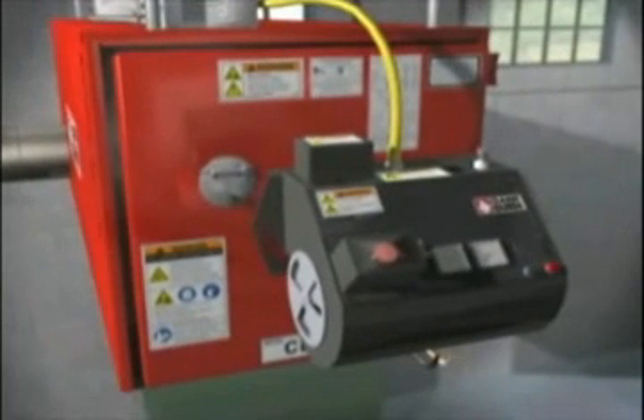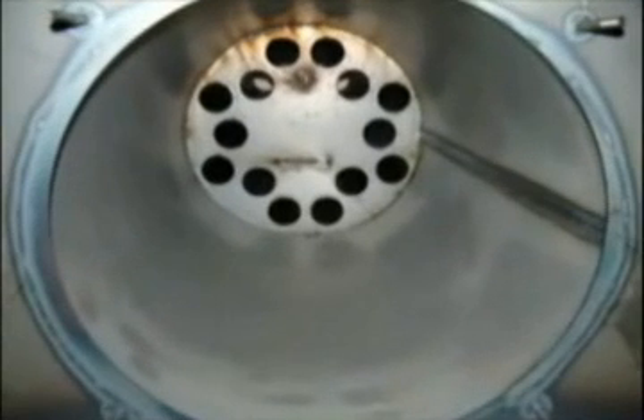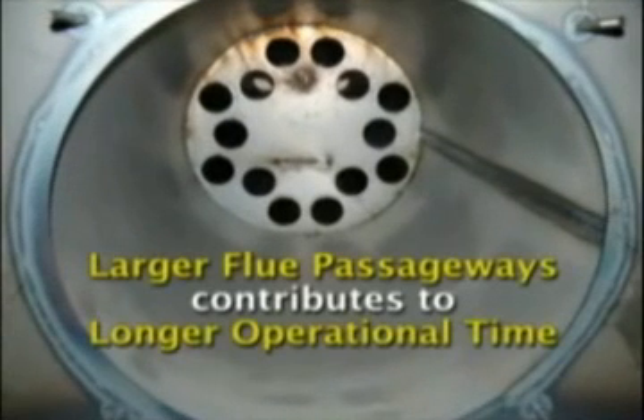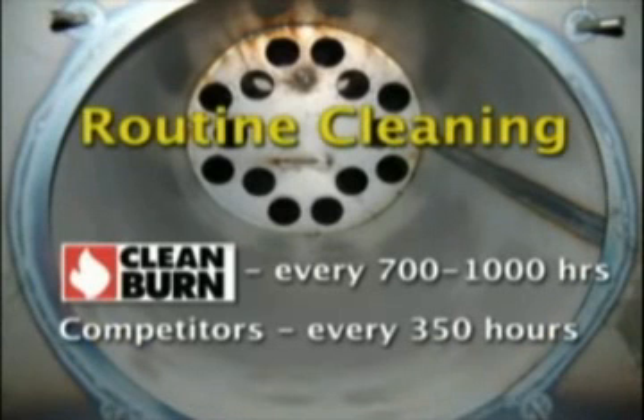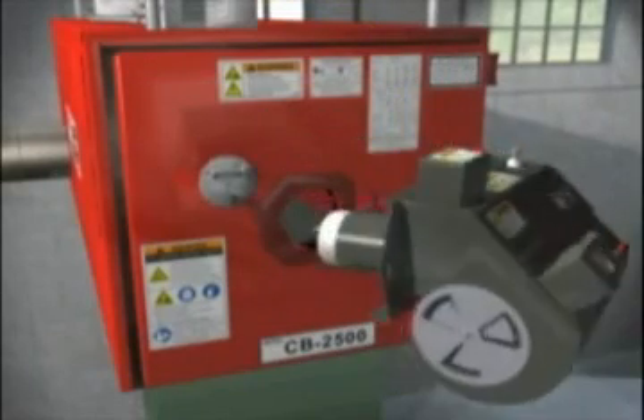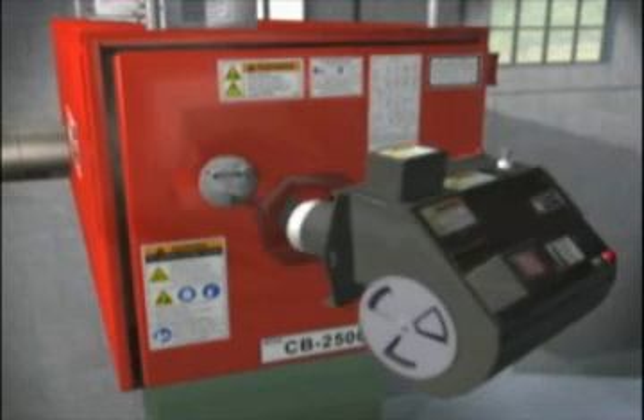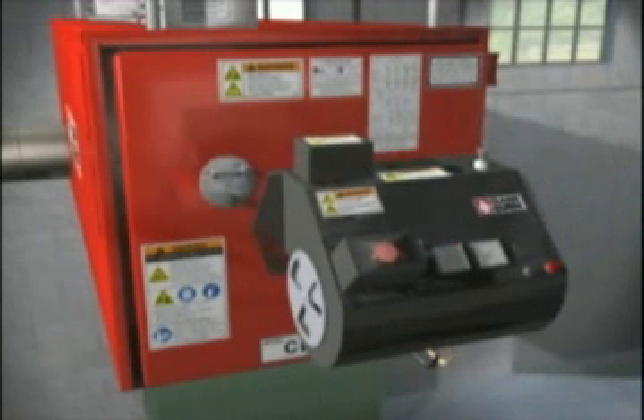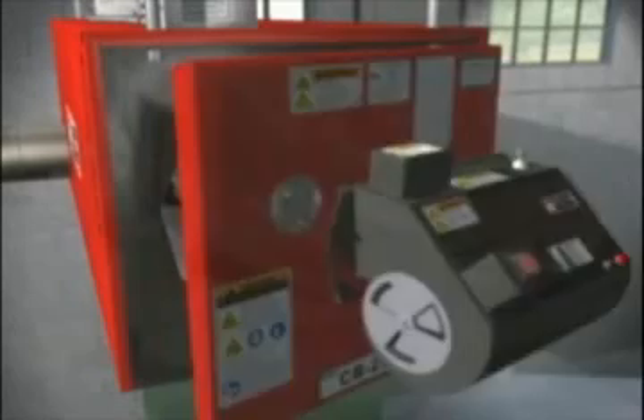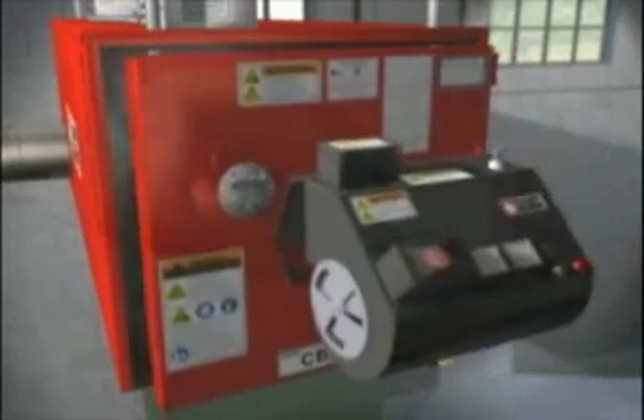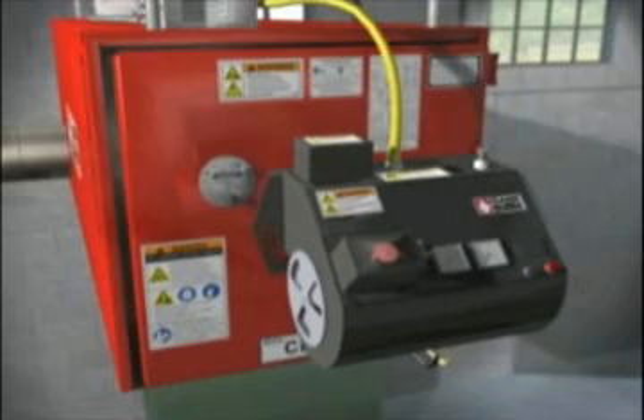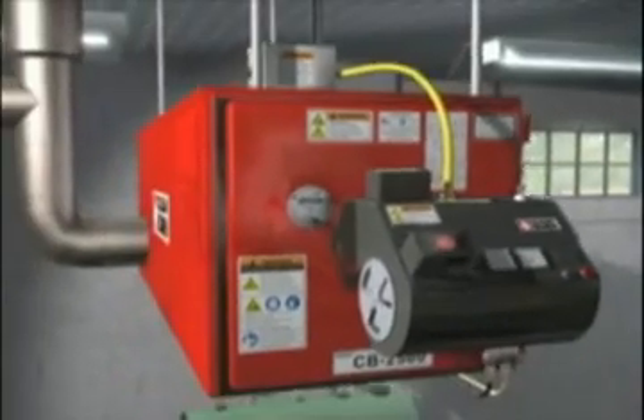CleanBurn makes routine maintenance truly routine. Their flue passageways are larger than on most competitive furnaces and results in longer operation time between routine cleanings. On average, a CleanBurn furnace requires cleaning only every 700 to 1,000 hours, as compared to every 350 hours for many competitive units. CleanBurn's swing-away burner design provides quick, easy access to the burner with no need to disconnect the oil and air lines. There is also a swing-out burner door to provide quick, easy access to the combustion chamber. These unique modular design elements make service faster and easier.